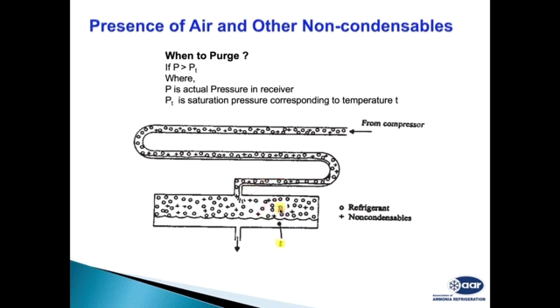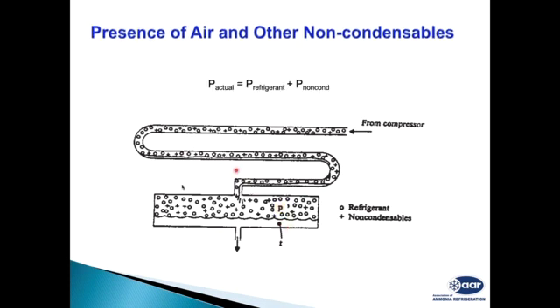Receiver pressure. So if you are able to measure receiver pressure and measure the temperature of the receiver liquid, convert that temperature to saturated pressure, and what is the difference? That is the air. This is our actual pressure measured on the gauge. This is our equivalent pressure of the saturated pressure of the liquid going into the evaporator. And the extra pressure that is showing is the non-condensable gases.